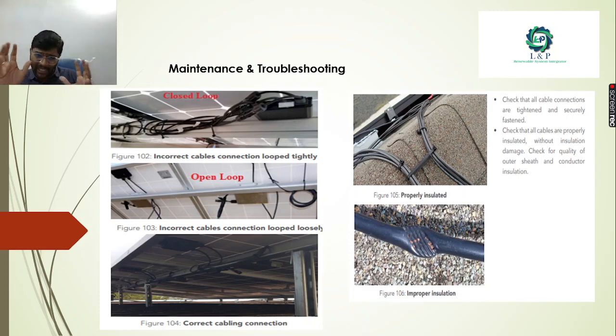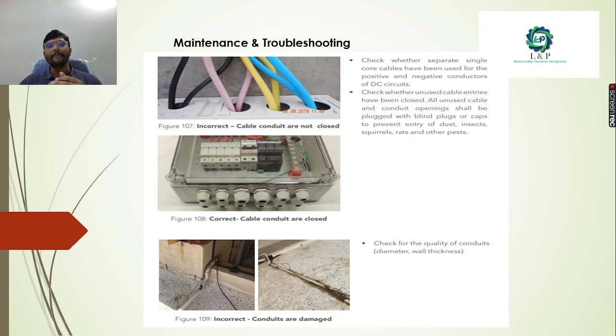Make sure the cable connections are made properly and that you have used cable ties for proper routing. If it is an improper installation, this is how you can see the conductors. Even very loose connections can cause damage and an open loop. Most importantly, whenever you are doing cable work, make sure the cable conduits are closed properly, because even the side edges can damage your cables. Always route using conduits properly, and check whether any conduits are damaged. If they are damaged, you need to replace them.